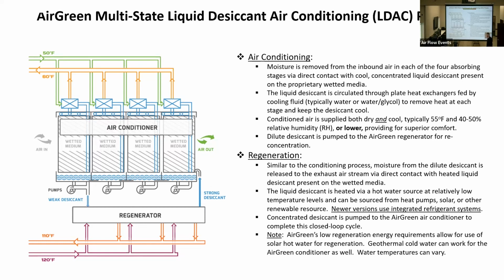Is the hot water, chilled water system the only manner of regenerating, or have you thought of anything else? No, we've been playing around with the refrigerant system today, and we're in a prototype building right now. I'll talk a little bit about it later, but the cooler you make the desiccant solution, the more effective it is. So we've gone from a heat pump system to a CHP or cogeneration system, which some of the cannabis guys do. The chilled water temperatures there are about 41, 42 for us. We get even more performance there.